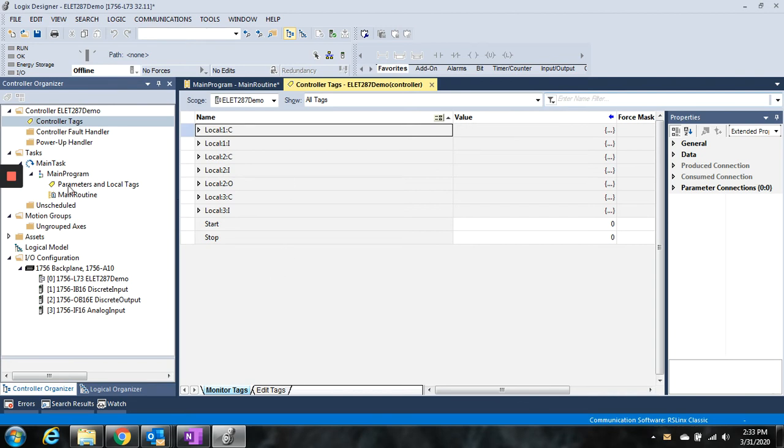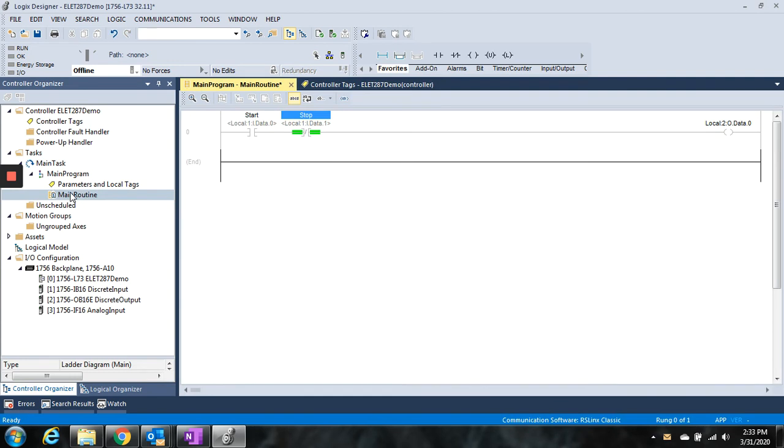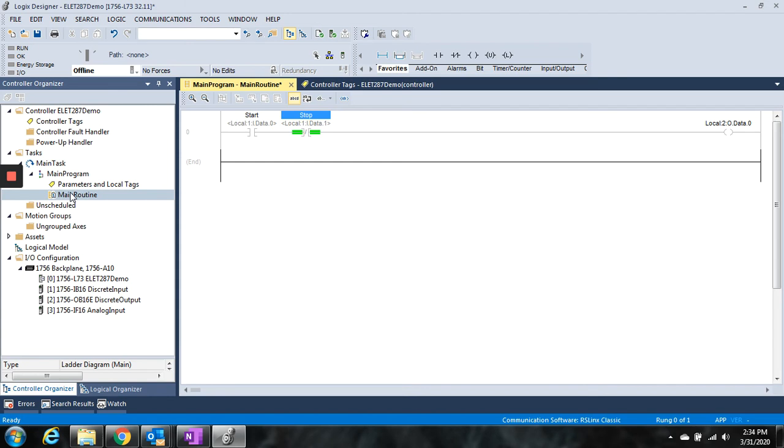So alias tags are just simply pointers to other memory spaces inside the controller. In the ControlLogix world, we don't have to know all the internal workings of the memory mapping. That controller tag database does that for us. We're going to just create tags and reference tags, and then the controller itself knows where the pointers are to go get the data from that tag. Hopefully this cleared up a little bit better. I know it's hard still. It would be so much more obvious and intuitive if we could actually connect to a real controller and let you play around with this. I think it would become very intuitive at that moment to see how it works.